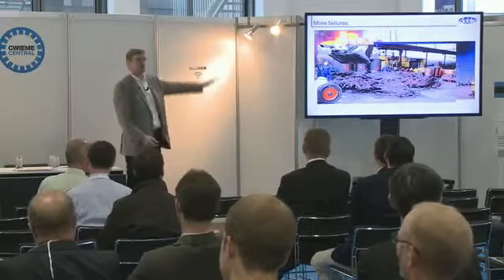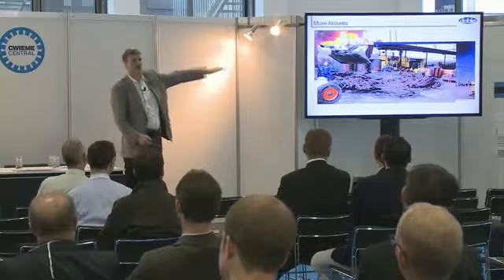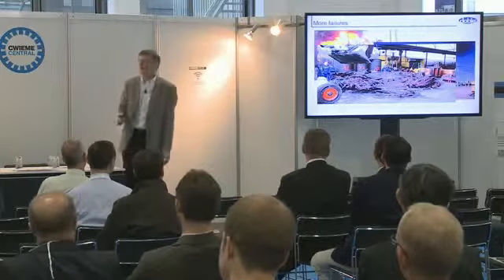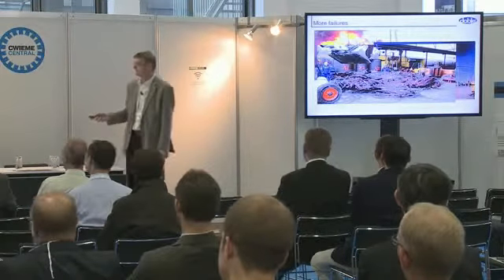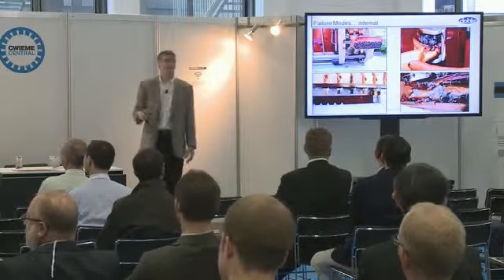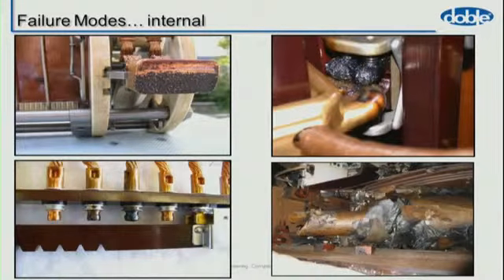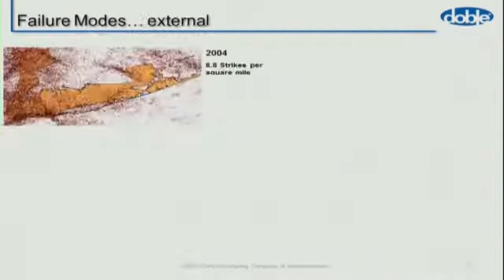I put this one here because they've marked the windings so that when they've taken them out, they can put them back in the correct order. Internal failure modes, coking on tap changers, overheating of windings at particular design spots. Lightning, if the lightning levels go up, you will have an increase in failures because you have more faults on the system.